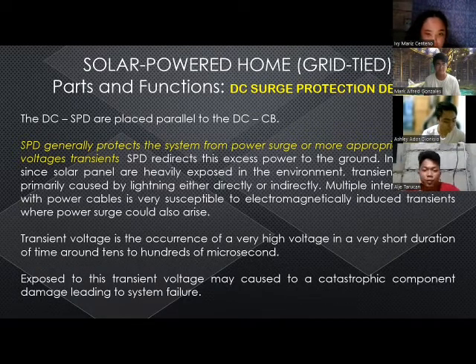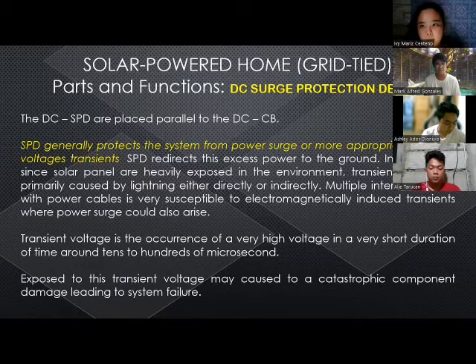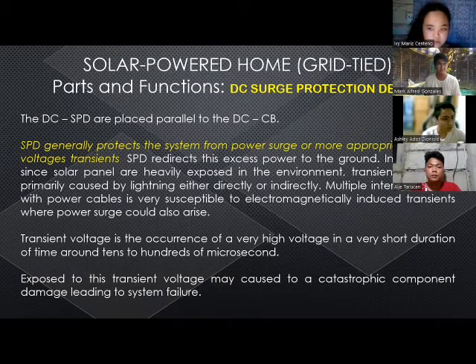So, the DC surge protection device, before the surge enters our system, prevents the sudden rise in voltage caused by the catastrophic event. It is on the DC side of the connection. SPD redirects this excess power to the ground. In a PV system, since solar panels are heavily exposed to the environment, transient voltage is primarily caused by lightning, either directly or indirectly. Multiple interconnections with power cables are very susceptible to electromagnetically induced transients where power surge could also arise. So, those are what we mentioned earlier.